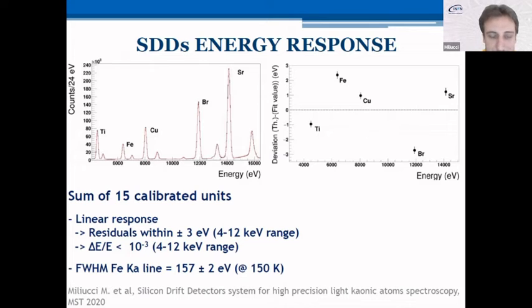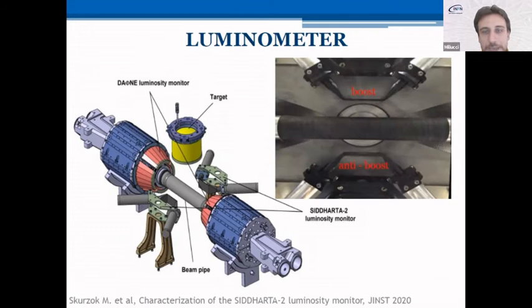And this is also demonstrated by the resolution of the K alpha line of the iron that we took as an example, because it's the reference value for the evaluation of the resolution of all the silicon drift detectors, which is 157 at 150 Kelvin. So it's completely in agreement and completely expected for this detector. So here we close the test that we have done in this heavy condition. And then we also installed and tested the luminometer, which is another fundamental tool to evaluate the quality of the beam.